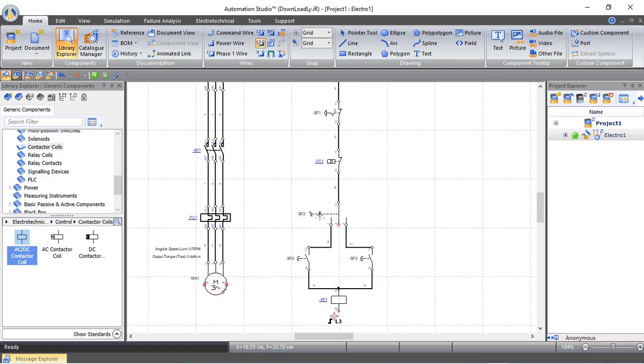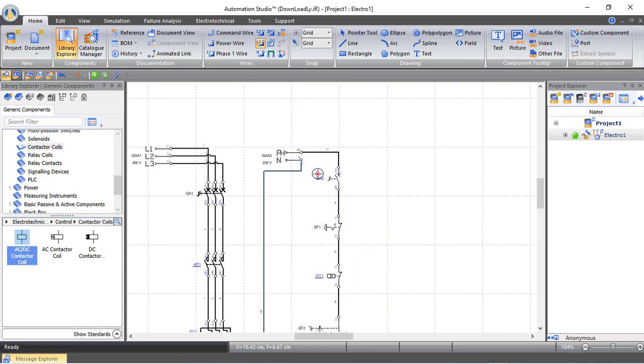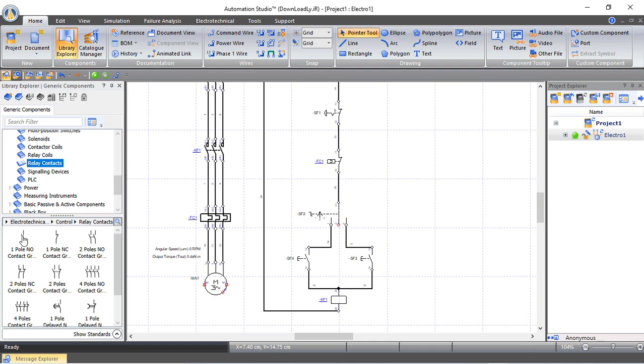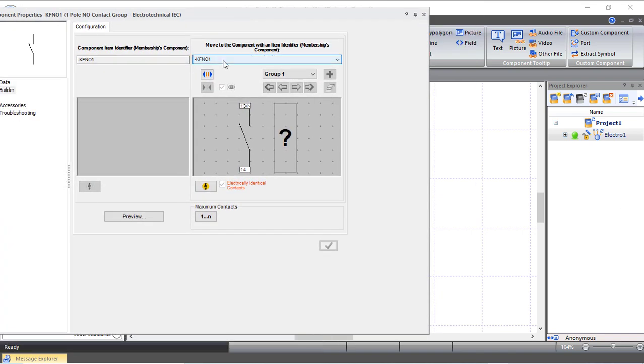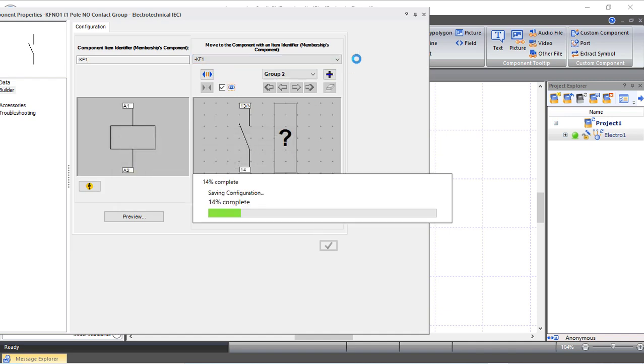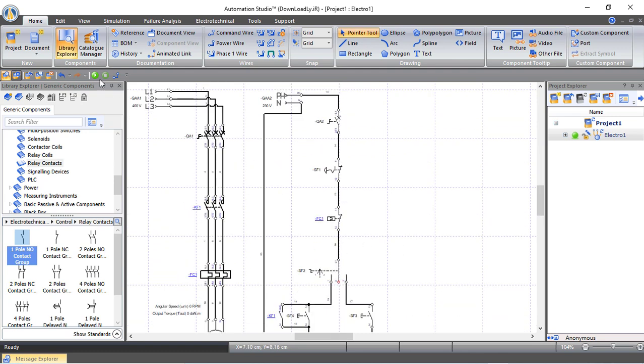The other terminal of the contactor coil connects to the neutral. From relay contacts we bring a normally open contact and connect it in parallel with the continuous push button to create a holding or latch contact. This contact is also connected to the KF1 coil, so when the coil is activated the contactor energizes and this normally open contact closes, latching the coil and keeping the motor running continuously.